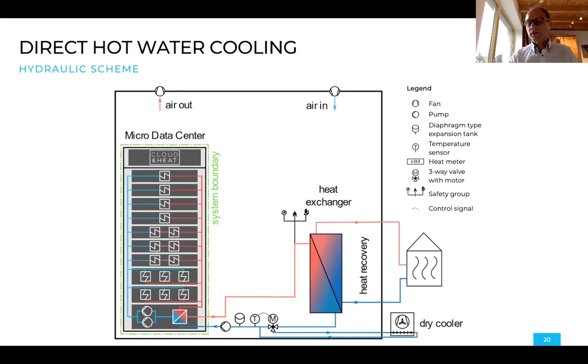Now, cooled down means, in our systems, the server needs a temperature of 55 degrees Celsius or lower, and that's cold enough to cool those servers. I'm talking about 55 degrees, so that's typically hot water, right? But 55 is cold enough with our technology to cool the servers. And the servers heat up this water from 55 to 60 or even higher, and this 60 degrees Celsius is hot enough to be used in a lot of applications and not to be considered as waste heat. If you have just warm air coming from a server, that has literally no value. You want to get rid of that, right? But if you have really hot water coming from the server, it suddenly begins to have a value because you can use it for other things. Now, how do we do that in detail? This is a server blade that consists of 2 CPUs, and we removed all fans on this server blade.